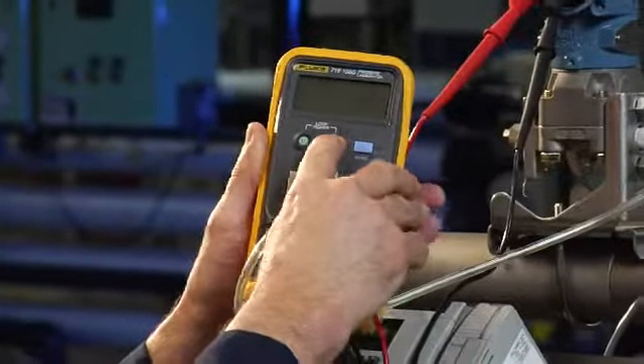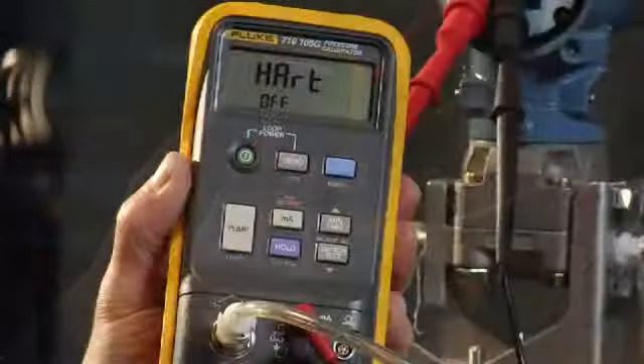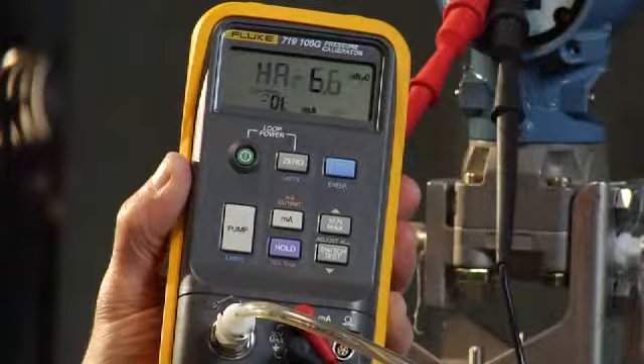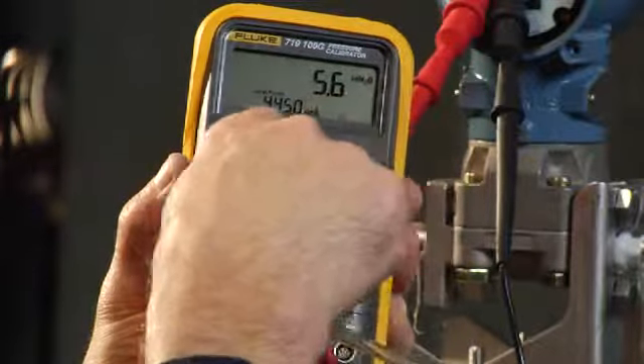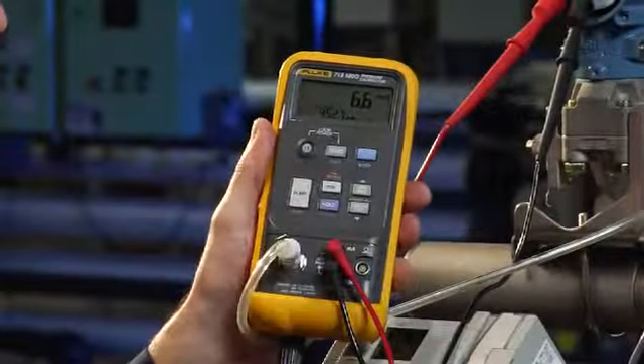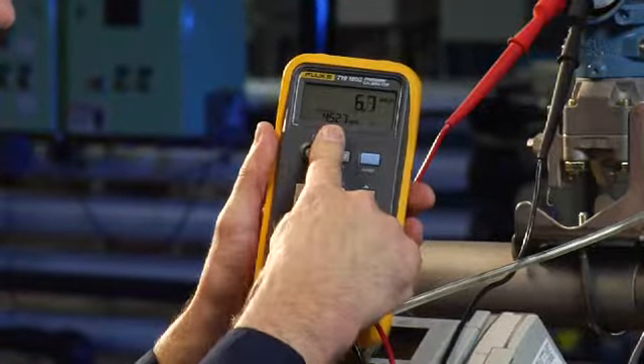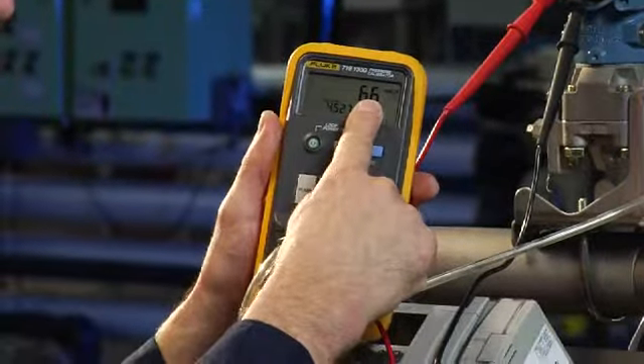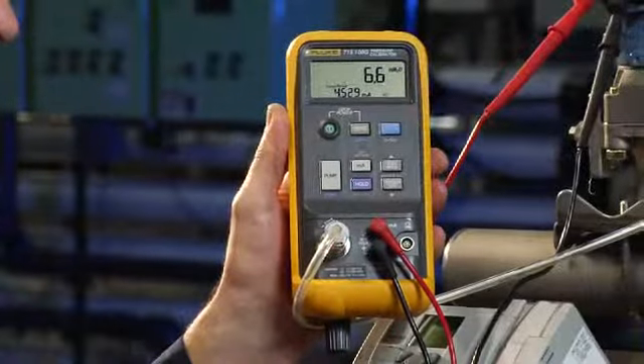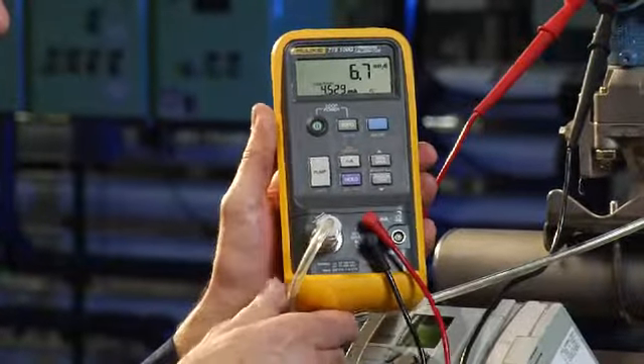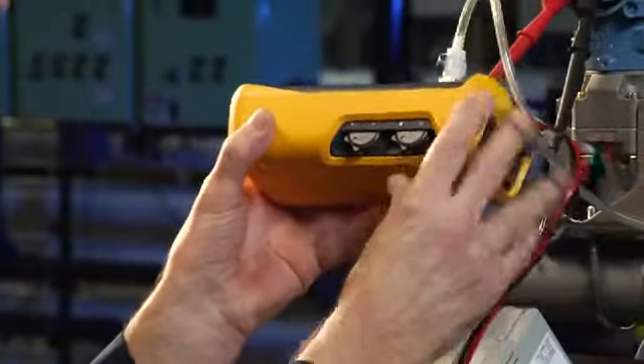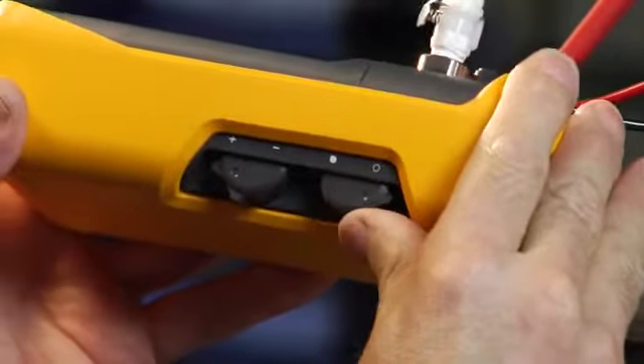Power up the transmitter with the loop power supply. We'll measure the milliamp signal drawn from the power supply that is provided by the 719. Initially, we see the milliamp signal being measured and the pressure that's being applied. In the first step, we want to measure 0 inches of water. The best way to do this is to vent to atmosphere. We do that with these controls.